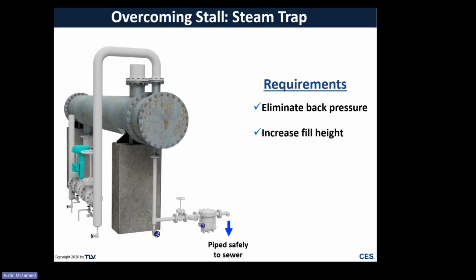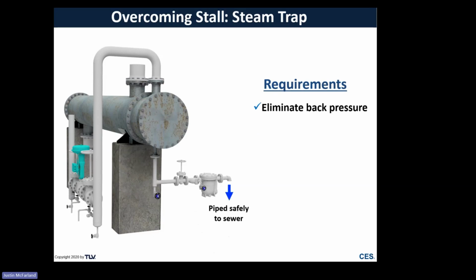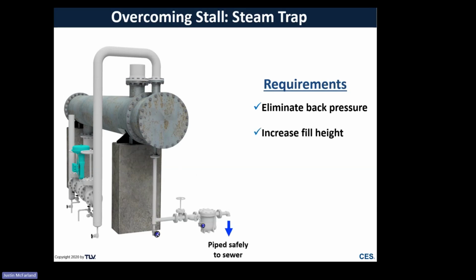In addition to that, doing some slight piping modifications. So going to basically drop that trap as far down as possible to increase the fill height. So what that does is allows a volume where condensate can back up, not necessarily into the heater itself, but in the upstream piping, remembering that for every 2 feet, we've got 1 PSI hydraulic head. So if we've got, let's say, 4 feet right here, well, that's 2 PSI upstream of the trap draining to atmosphere. That's a 2 PSI positive differential pressure. It's not much, but that's something that we can work with, and we can size a trap for that.